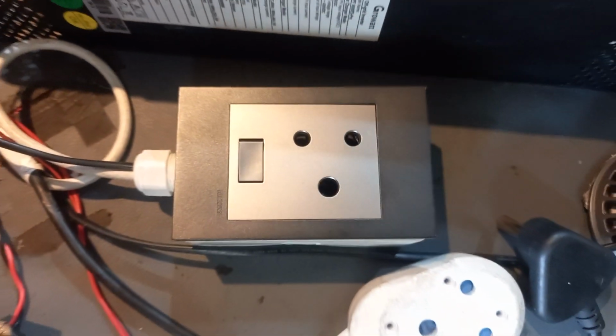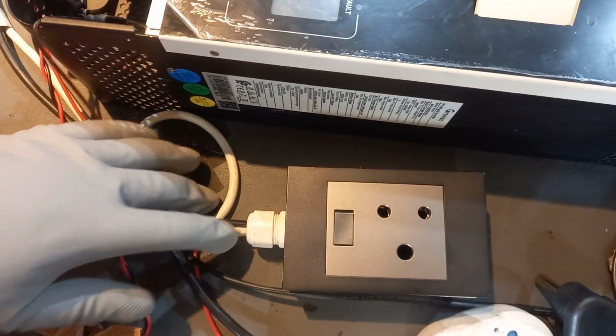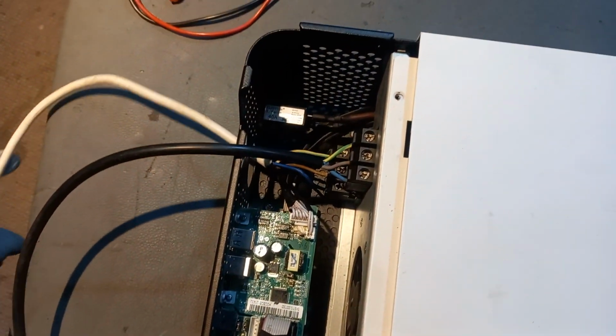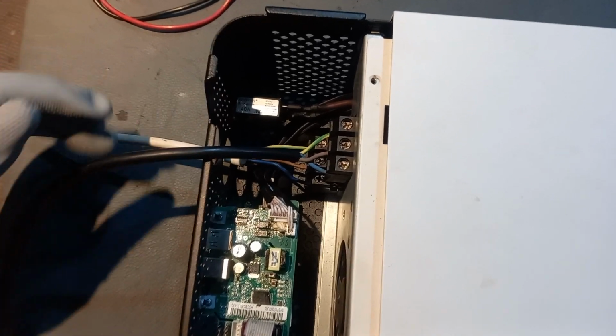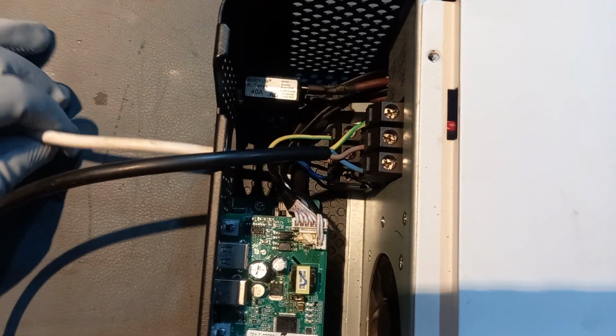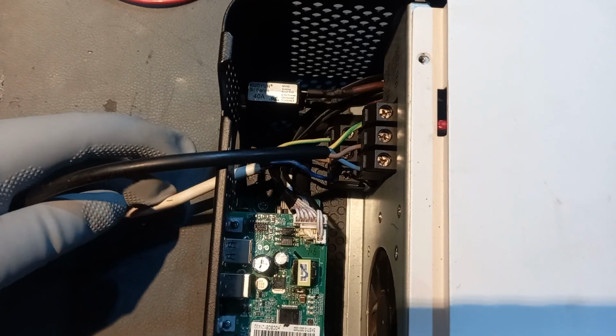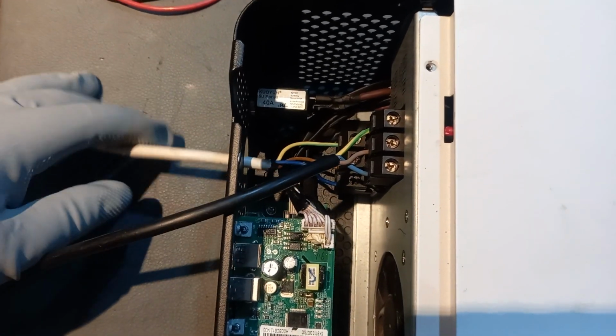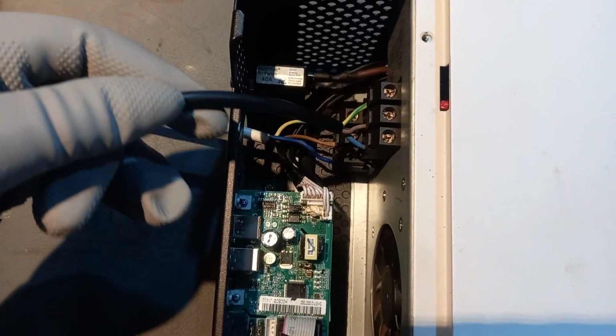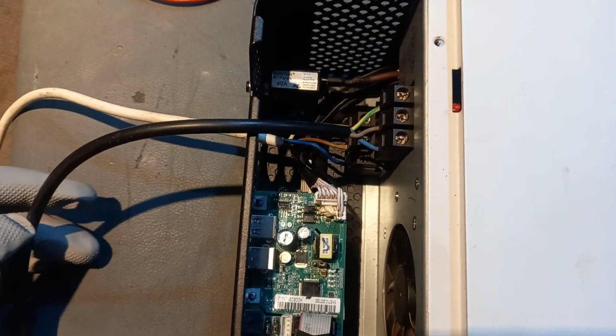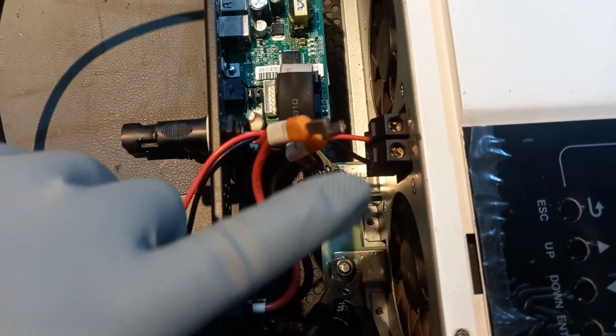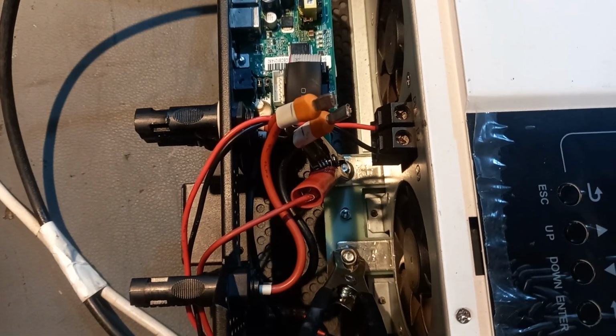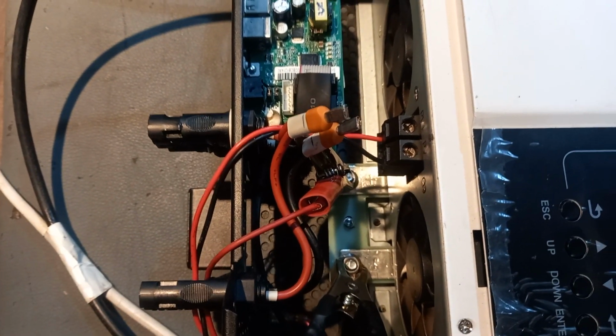We've got the light there. See that spotlight there? It's connected to the plug together, and the white cable goes straight to the inverter, which is the bottom terminal. You can see there. The bottom one is the line that's supplying the light, and the top one is the Eskom line, which is an input. Okay, and then we've got the PV connected as well. We are going to test those, and the battery connected already.